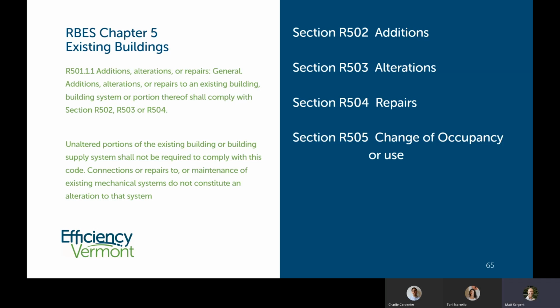So Chapter 5 applies to existing buildings. 501.1.1 stipulates that alterations, additions, or repairs to an existing building system must comply with those sections of our Chapter 5, our 502, 503, and 504. Unaltered portions of the building are not required to comply with the code. Connections or repairs to or maintenance of existing mechanical systems don't constitute an alteration to the system and therefore don't need to comply with the code.